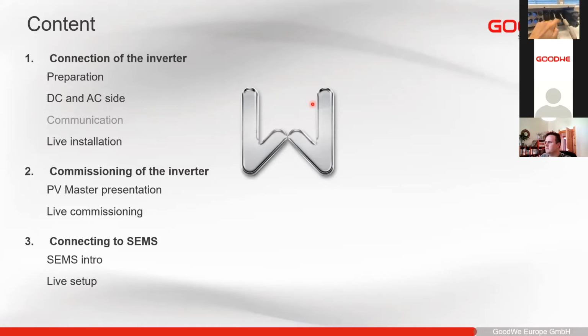This is the older version of the ET inverter. So instead of having one port here with all the connections, we have the BMS here, the meter here, and here on the bottom side we have the RS485 for connection to, let's say, the SEC 1000S if you want to connect multiple ETs in parallel. And here we have then the AC connection. I can remove this so you see the connection. So here you have one here on the top, it says on grid, and here on the bottom side, below you can see it says backup. And then you see the different connections you need to connect.